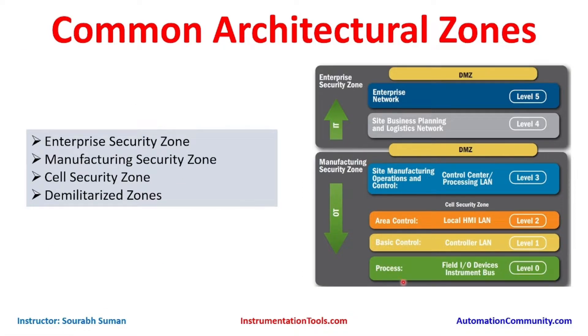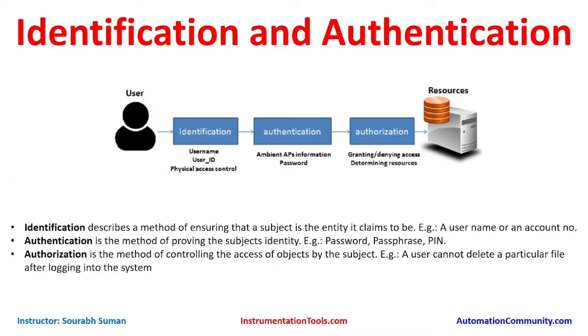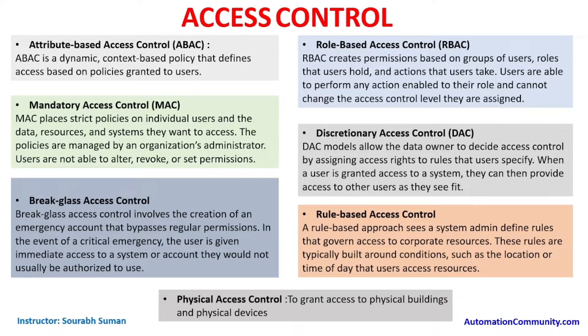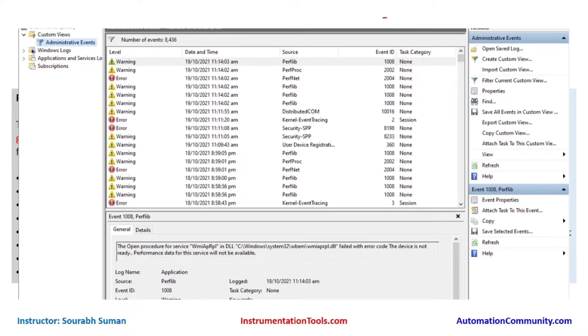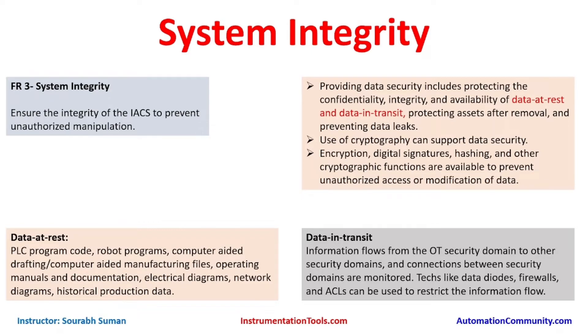We covered common OT network zones: the manufacturing zone, cell security zone, and enterprise zone for IT/business communications. Once that foundation was set, we studied the seven foundational requirements per IEC 62443. The first was identification and authentication — what identification is, what authentication is — and then types of access control and use control, including non-repudiation and time synchronization.